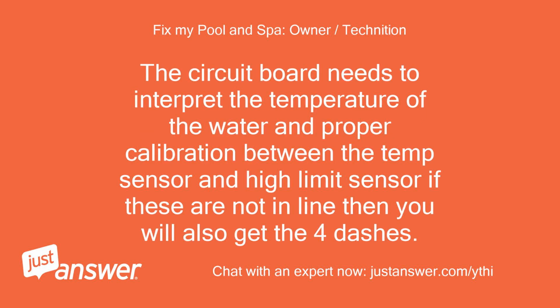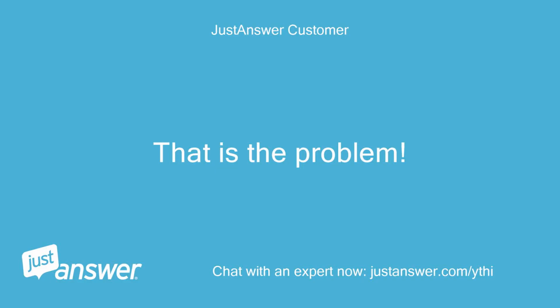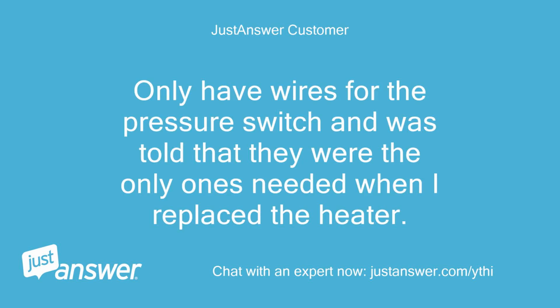The circuit board needs to interpret the temperature of the water and proper calibration between the temp sensor and high limit sensor. If these are not in line, then you will also get the 4 dashes. That is the problem. I only have wires for the pressure switch and was told that they were the only ones needed when I replaced the heater.